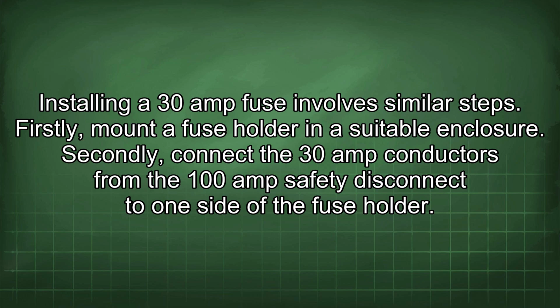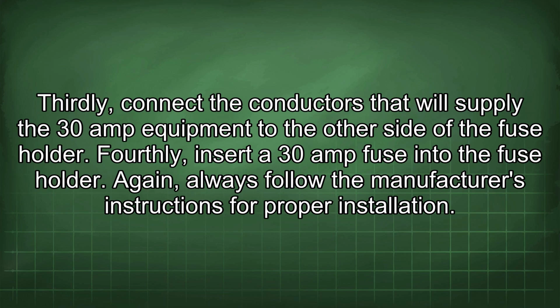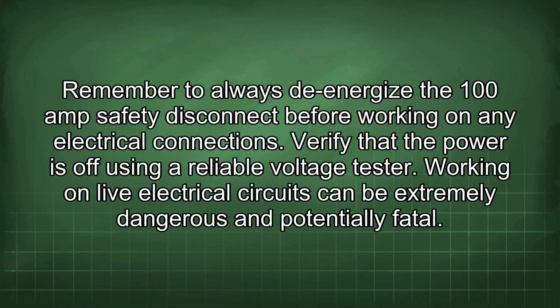Installing a 30 amp fuse involves similar steps. Firstly, mount a fuse holder in a suitable enclosure. Secondly, connect the 30 amp conductors from the 100 amp safety disconnect to one side of the fuse holder. Thirdly, connect the conductors that will supply the 30 amp equipment to the other side of the fuse holder. Fourthly, insert a 30 amp fuse into the fuse holder. Again, always follow the manufacturer's instructions for proper installation. Remember to always de-energize the 100 amp safety disconnect before working on any electrical connections. Verify that the power is off using a reliable voltage tester. Working on live electrical circuits can be extremely dangerous and potentially fatal.